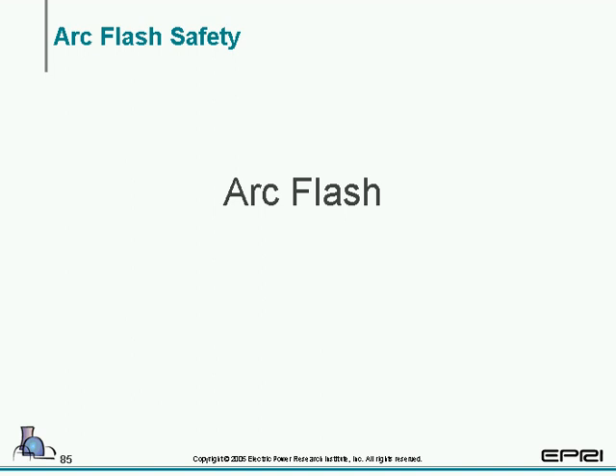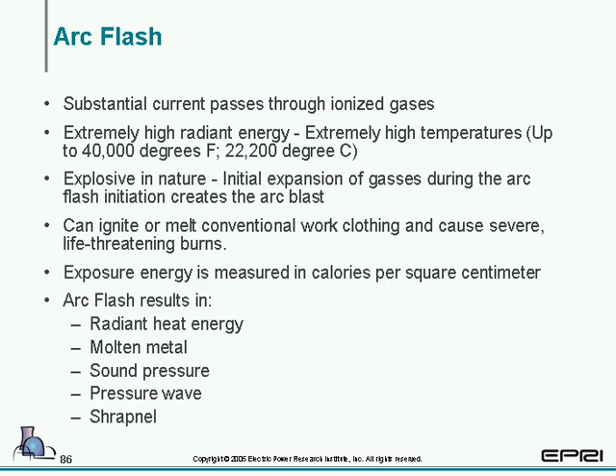Moving on, this is the final section. We're going to talk about arc flash. Just going to hit the highlights here because we're limited on time. And an arc flash, trying to define what an arc flash is, it's basically substantial current passing through ionized gas. It's extremely high radiant energy, extremely high temperatures, up to 40,000 degrees F, 22,000 degrees C.